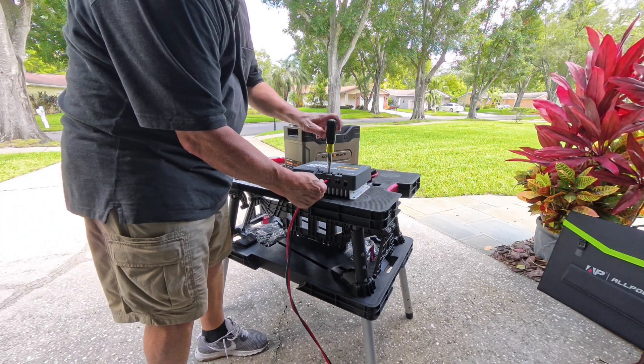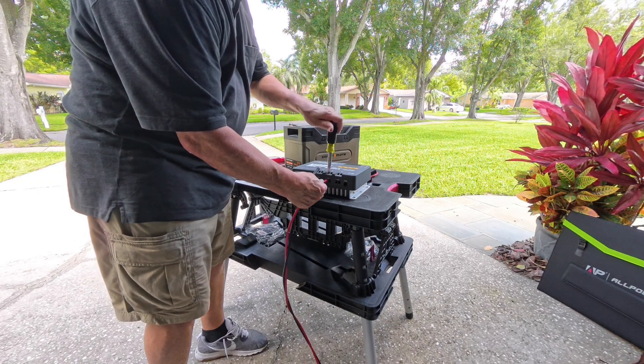I am interested in some comments and feedback, because I didn't find this to be as successful as I had hoped. It worked better than just jamming the stranded wires into the charge controller receptacles, but even when I torqued down on them I really wasn't happy with how much these ferrules deformed. So if you have some experience with this, please make a comment below — are there different grades of quality with these ferrules? Do they not deform even after you torque down on them, or is deforming just what I should expect? I don't use these a lot, but it is the appropriate way to go about this, so I'm looking for you to educate me.